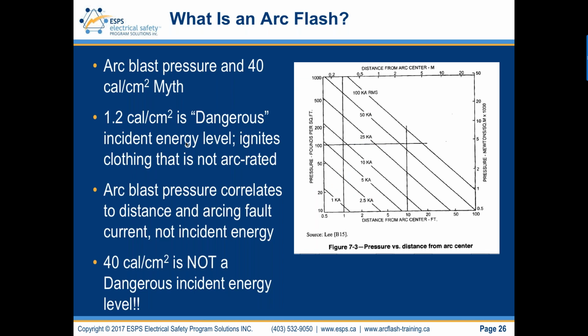Arc blast pressure, very controversial, and I'm outspoken in this area. So if you haven't heard this before, arc blast pressure and what I call the 40 cal myth: 40 calories per centimeter squared is not a dangerous incident energy level. If we have to classify a dangerous incident energy level, let's say 1.2 calories per centimeter squared and greater, right? Sorry, let's go back. At 1.2 calories per centimeter squared, that's a dangerous incident energy level because at higher than that level, it will ignite clothing that's not arc rated. Arc blast pressure correlates to distance and arcing fault current, not incident energy. 40 calories per centimeter squared for the last decade has been miscommunicated as a dangerous incident energy level.